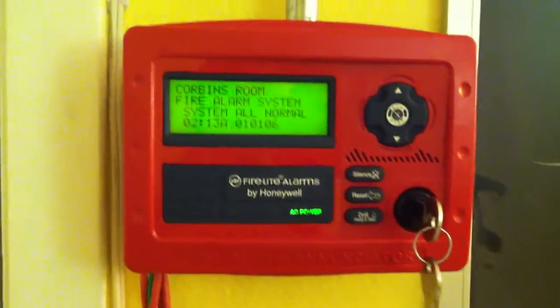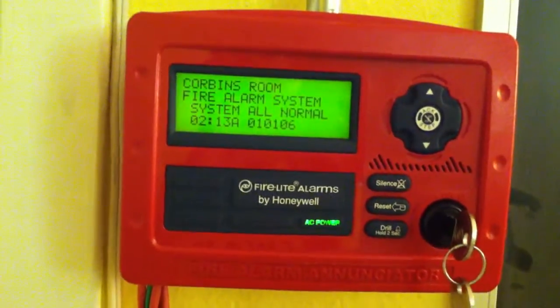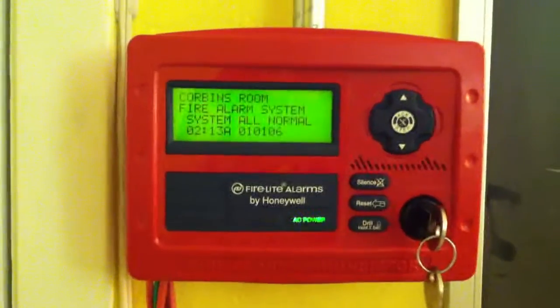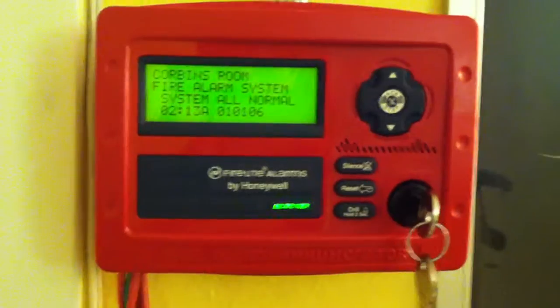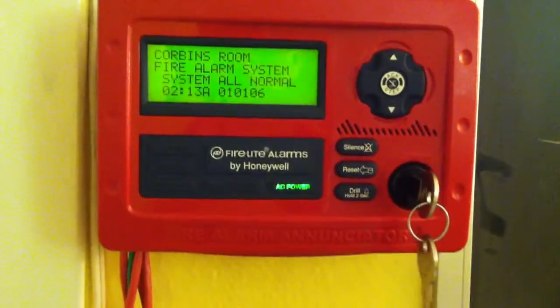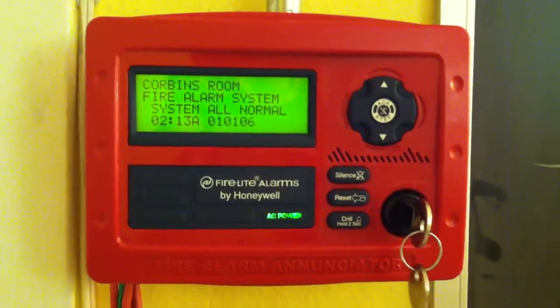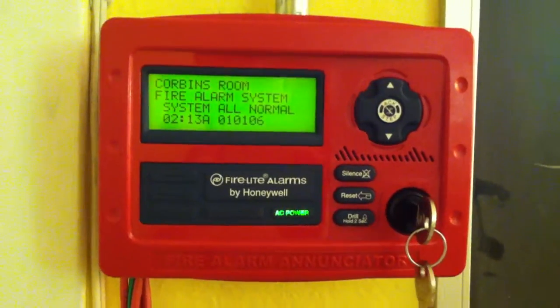Hello guys, so I tried doing the drill function on the Fire-Lite MS-9050UD, and for some reason the horns are the only things that sounded — the strobes did not flash. So I looked in the manual for the MS-9050UD by Fire-Lite, and it said that during drill mode, the non-silenceable NACs do not activate.